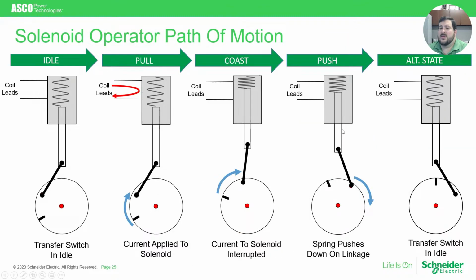Now, how exactly does all this motion happen? How does all this mechanical motion happen within the switch to open and close these contacts? Well, the transfer switch relies on the solenoid operator. There may be one, there may be two in the equipment, but the concept is the same. If you imagine the contacts mounted to a shaft, that shaft is represented by the red dot in this solenoid operator example. That shaft is mounted to essentially a wheel that is connected by a shaft to a pin that is inside an electrical coil. So this gray box is really an electrical coil, and this squiggly line here represents a spring inside the coil.